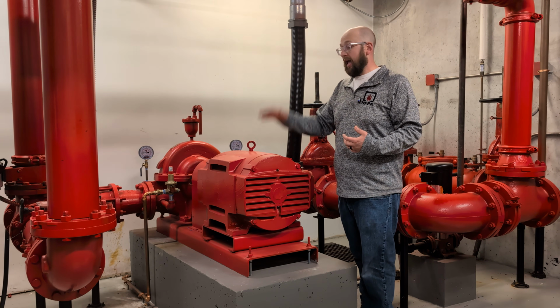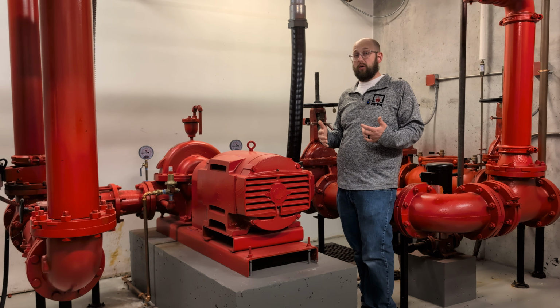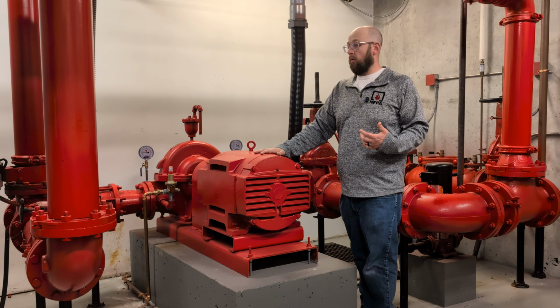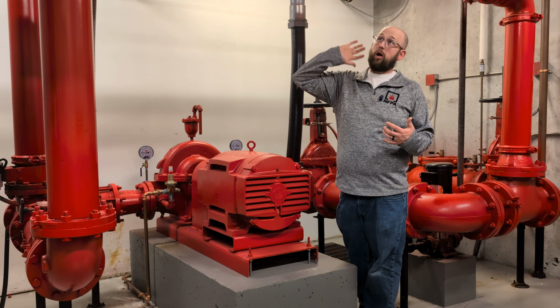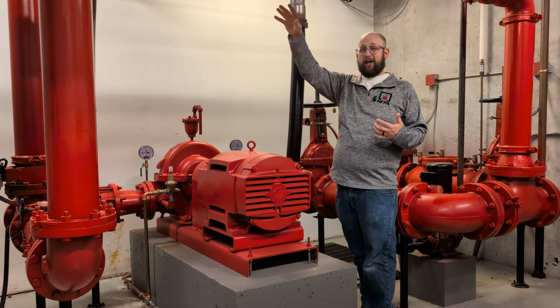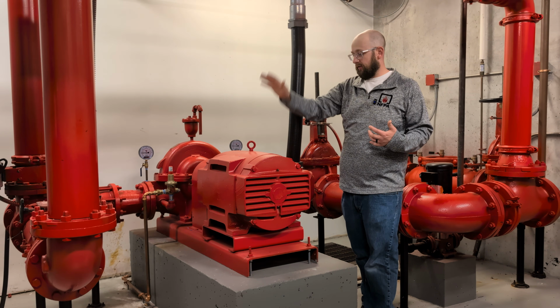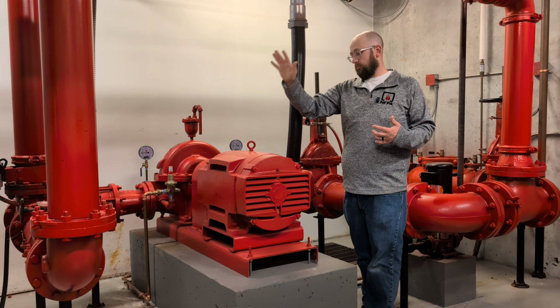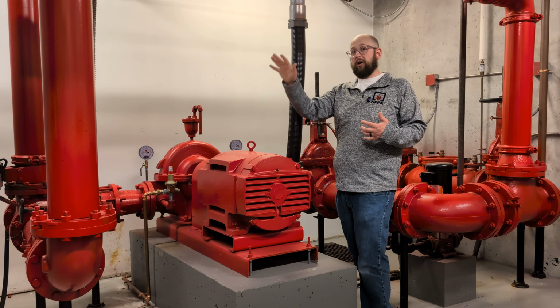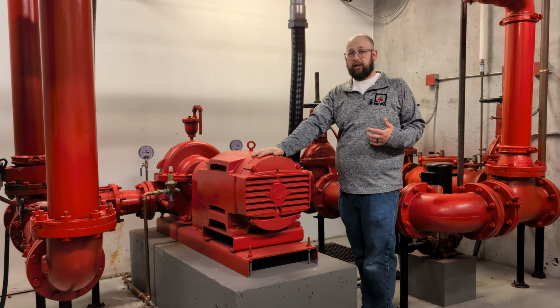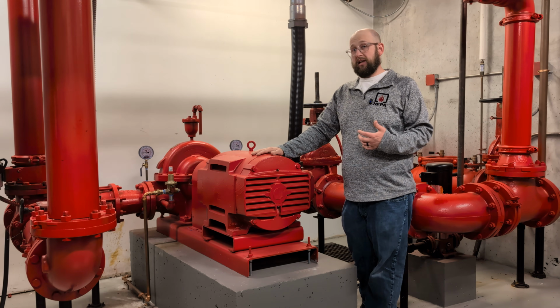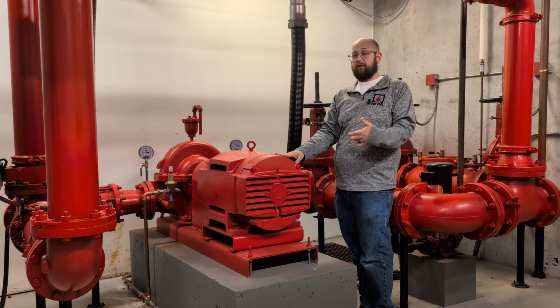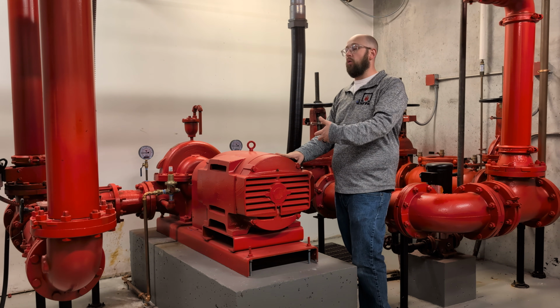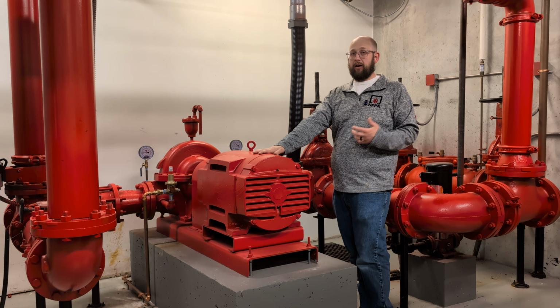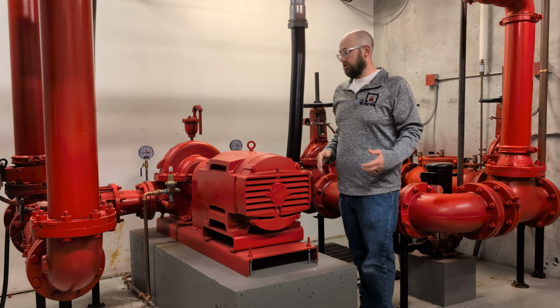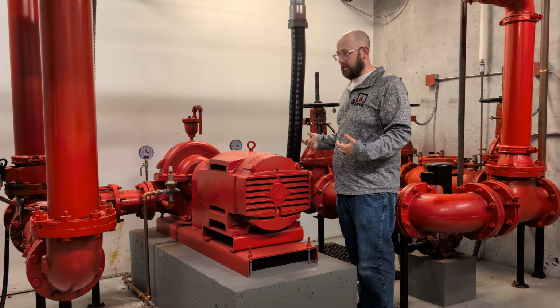And then on an annual basis, we're going to do an annual performance test where we're flowing water out of the building. All buildings are going to have what's called a test header outside the building to allow us to flow. We're going to flow a churn, then we're going to flow 100% of the capability of the fire pump and 150% of the capability of the fire pump. And we're going to confirm that we're getting the required pressure and flow out of the fire pump that we need for the system. So that's just an example of some of the inspection, testing, maintenance that we're doing on the fire pump.